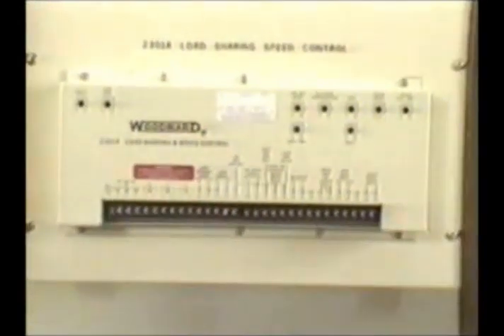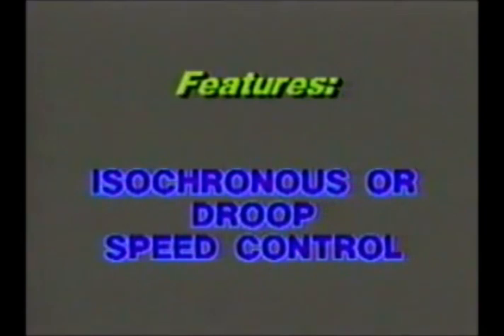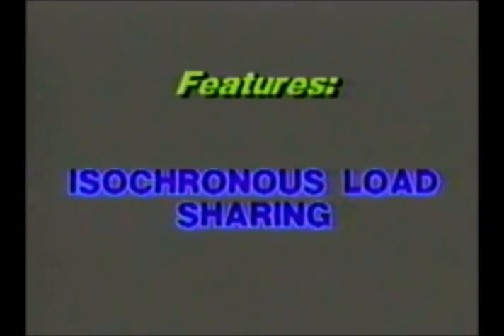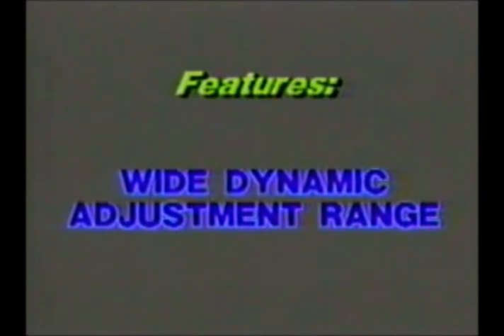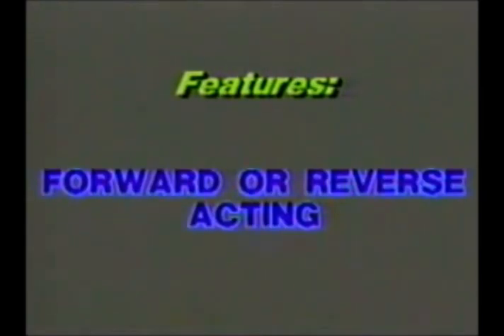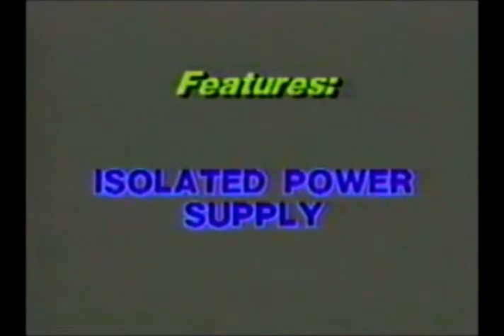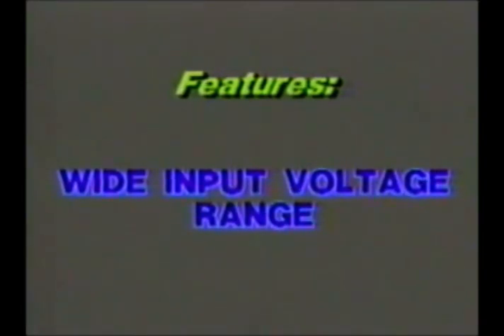The 2301A load sharing speed control can regulate speed and load for a variety of prime movers. This includes gas or diesel engines or steam and gas turbines. The 2301A has standard features of isochronous or droop speed control, isochronous load sharing, a wide dynamic adjustment range, and forward or reverse acting models. The power supply in the 2301A will eliminate ground loop problems. The input voltage for a 2301A will vary from 20 to 45 volts DC.